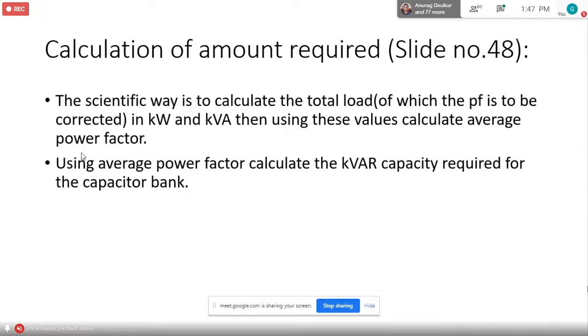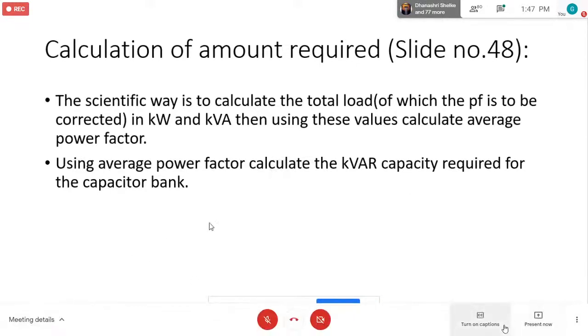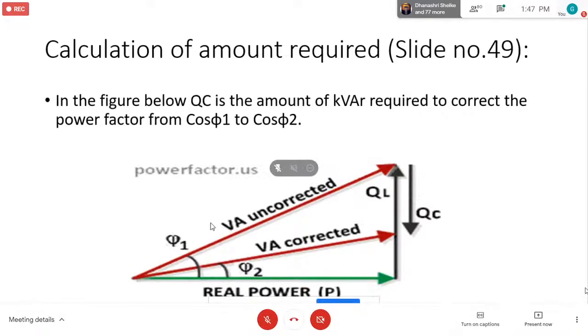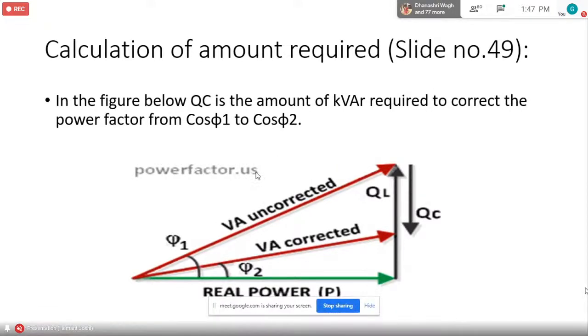Calculation of amount required. The scientific way is to calculate the total load of which the power factor is to be corrected, in kW and kVA, and then using these values calculate the average power factor, kW by kVA. Using the average power factor, calculate the capacity to be provided in the capacitor bank. So this is what you have been told in the books. This is the original kVAR, this is the capacitor one, and this is the final, so it will get you the required power factor. This is the method in the books.